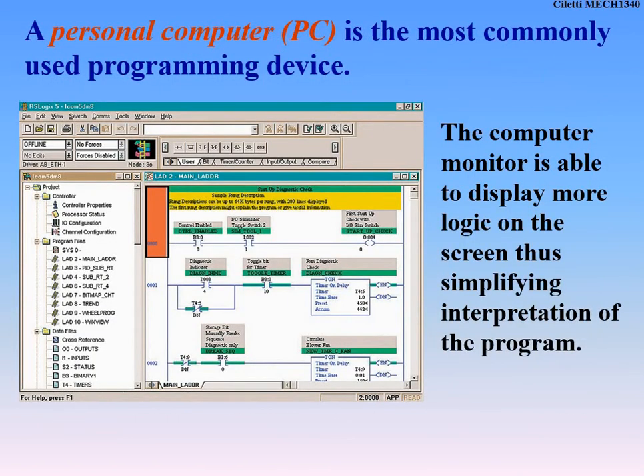Everything you'll see in my lecture is tied to our textbook, which is all Allen Bradley, so there will be some differences between my lectures showing Siemens versus showing Allen Bradley from the book. This uses Allen Bradley RSLogix 5 software. We can monitor live — when we hook up our laptops, program the PLC, upload it, and go live, we can actually monitor what the PLC is doing in real time. In Siemens, it shows a nice green or red color so we can see what's live, what's on, and what's off. I can monitor from home using the IP address of our Siemens 1500.